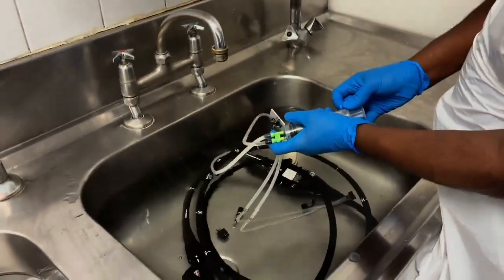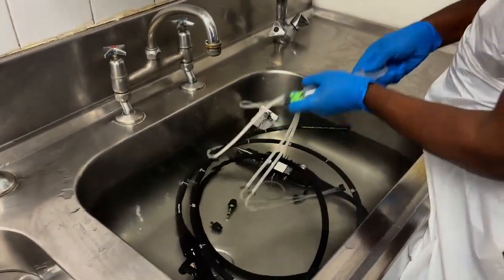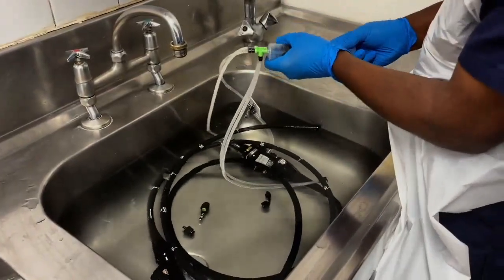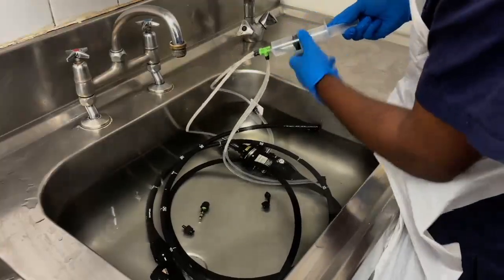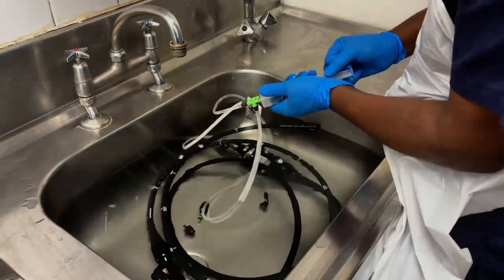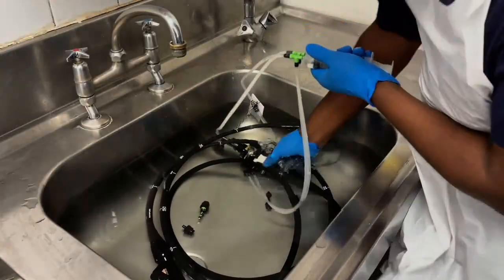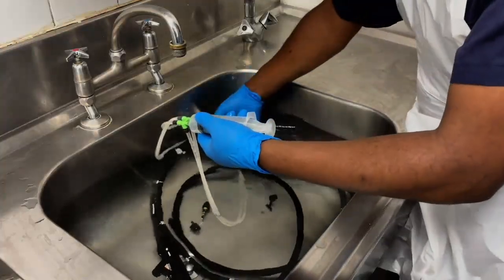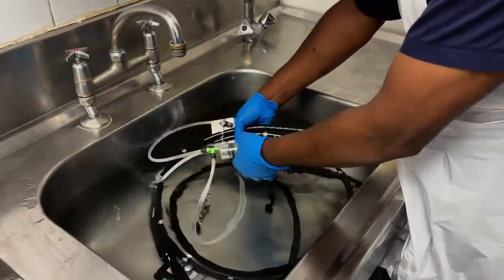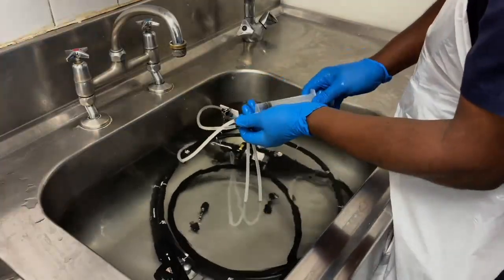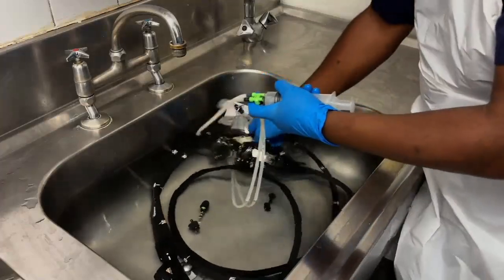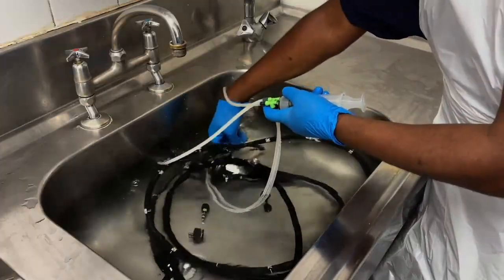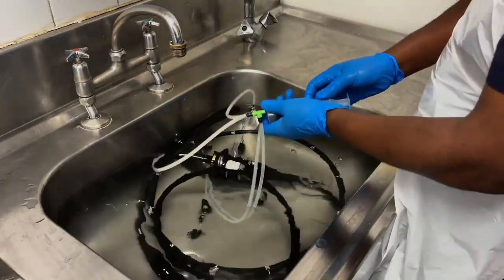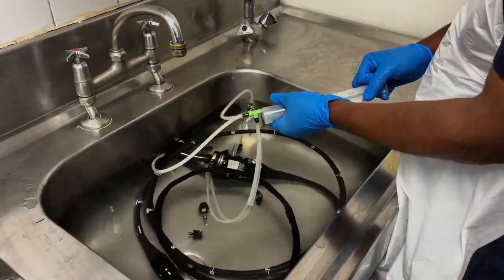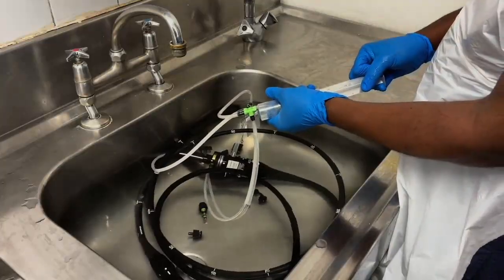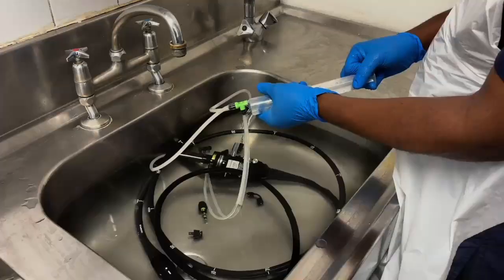Once the scope has been thoroughly cleaned, we need to move the scope to the rinse water. Always prepare a fresh batch of clean potable water. Submerge the entire scope in the fresh water. And rinse all the channels as per the manufacturer's instructions for use. Depending on the manufacturer, you may need to irrigate 2 or 3 times, perhaps with 20 mils, 40 mils, 60 mils, depending on those instructions. Clean potable water each time.